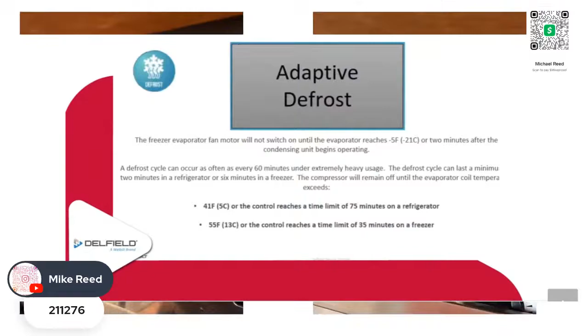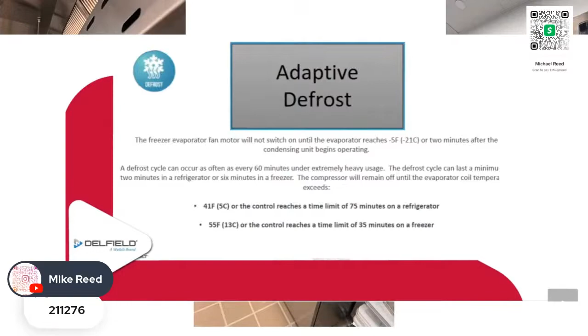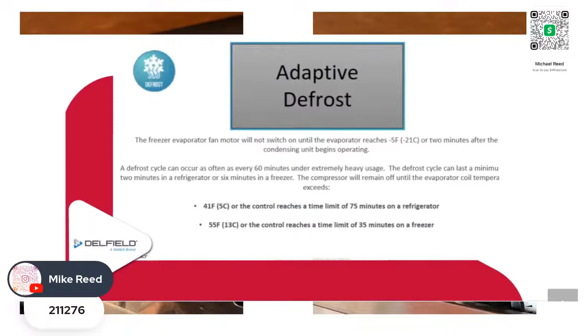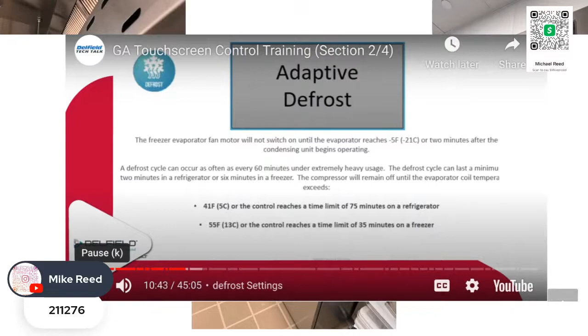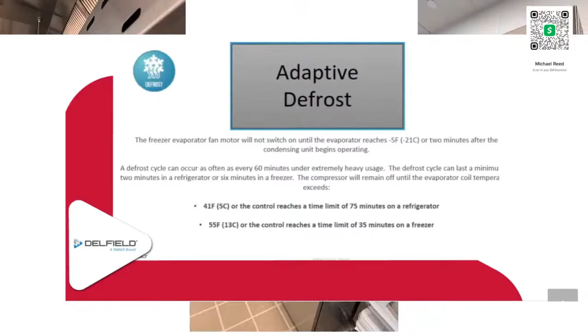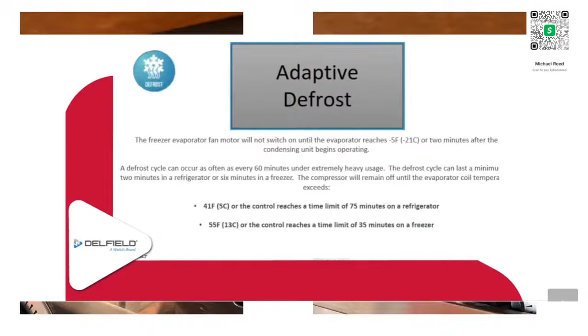Defrost on these units can happen just about every hour, depending on usage. We have a minimum defrost time of 2 minutes for a refrigerator and 6 minutes for a freezer, triggered if a low enough coil temperature is picked up. If the display or control is set quite low, it will kick into defrost a lot more frequently, especially in areas with a lot of door openings.